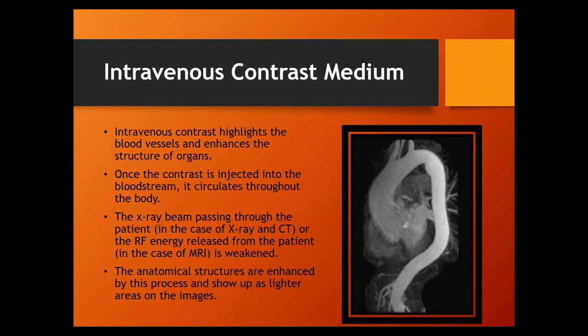One thing to remember is that injecting contrast is a timed process. The patient is alive and their heart is beating, so every second the contrast moves. We inject contrast and it's there for literally one second, then the heart beats and it moves. There has to be some timing between the imaging system and the injector to capture the shot at the particular moment the contrast is in the target blood vessel. It's not difficult, but there is coordination and timing involved.